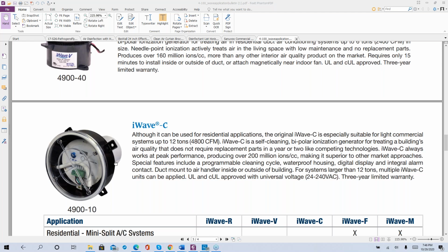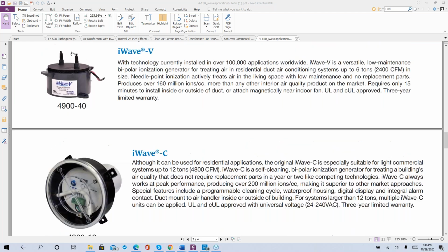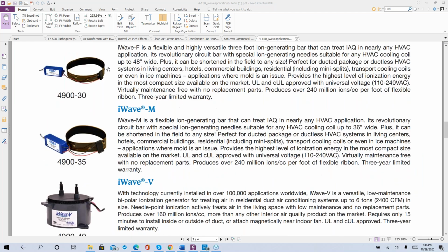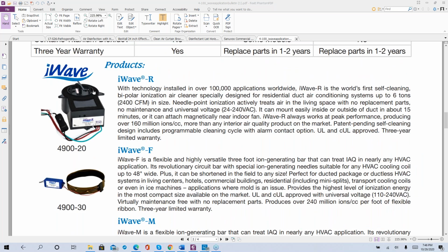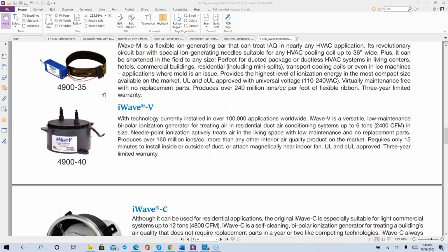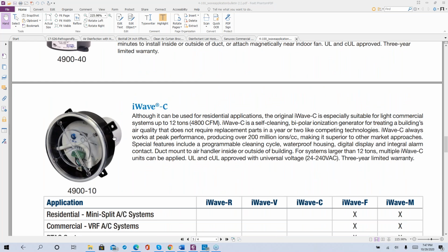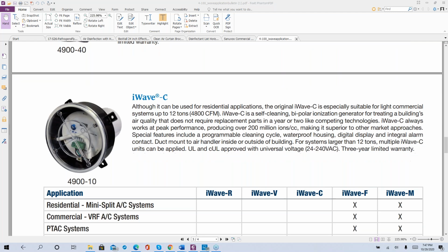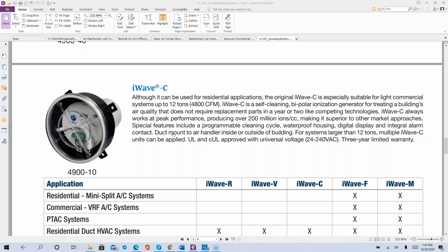So we'll put these in the supply duct. And the reason why goes back to that comment I had about the 2 inches to conductive material. This one has a much larger, almost 3 inches, 3 to 4 inches. And then the brushes are inside this white cone area. This also gives you an hour counter so that you'll know how many hours it has been operating, whereas the other ones do not. And this will do up to 12 tons or 4,800 CFM of airflow.